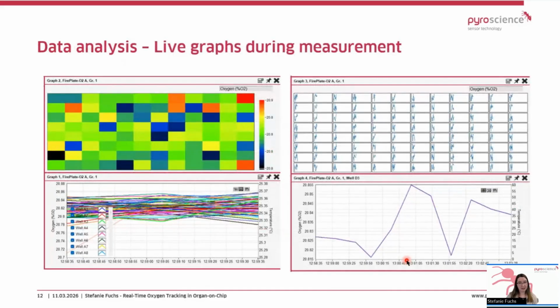Afterwards, you can then start a real measurement, and you already get during the measurement all these live graphs. So we have, for example, a heat map where you can then look if some chips do something else, and you might want to react to that. For example, you can also have a multi-graph where you can see all 96 sensors at once, or with the chips, it might be a few less. And then also this multi-graph where you can then also click on one of them. They are in the same positions as the wells on the well plate. And then you can just get a zoom in on this individual graph. So that is very convenient if you want to take a closer look at one of the sensors.